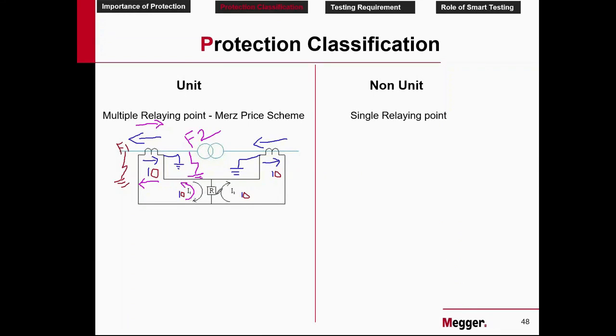So this will flow like this. If this flows like this, you can see it is adding. That means 10 plus 10, now it will become 20. So what we find here is when the fault is inside, that is between your compound wall, inside your CT, the current direction changes as defined by the Merz-Price scheme, and the relay will issue a trip command.